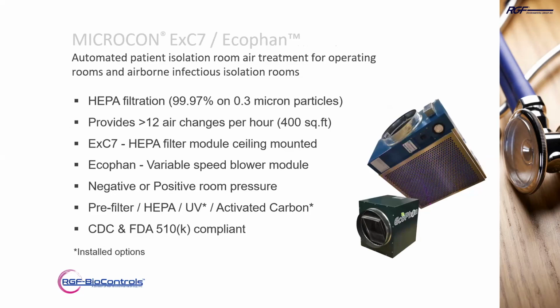The EXC7 is more of a permanent isolation room. Again we've got the HEPA, getting down to 0.3 microns, providing over 12 air changes per hour as required. The nice thing is the dimensions match the ceiling tiles in most hospitals, so you can just take the tile out. Since it comes with its own variable speed blower, we don't have to tap into or modify the existing HVAC equipment to install it. And again, it's CDC and FDA compliant. Next slide.